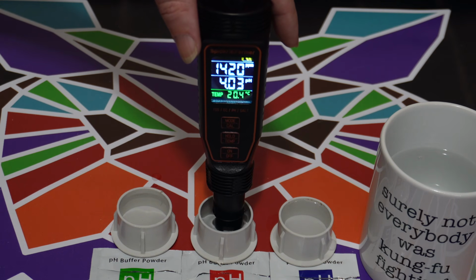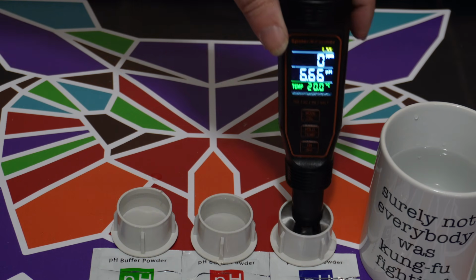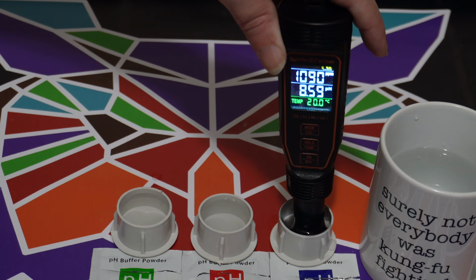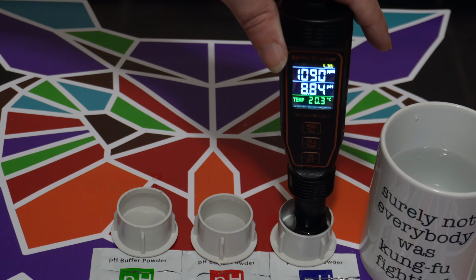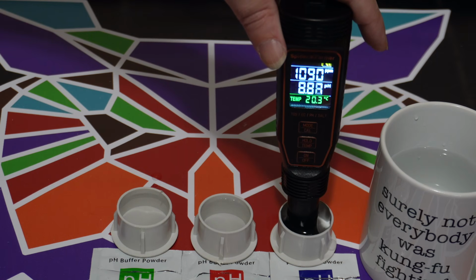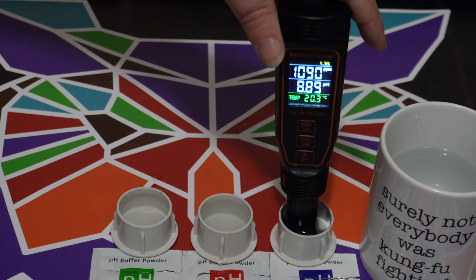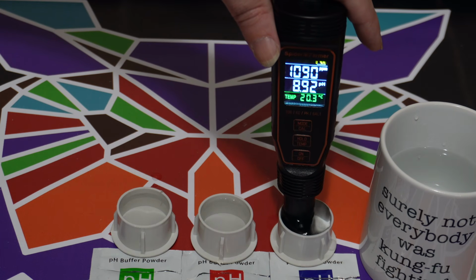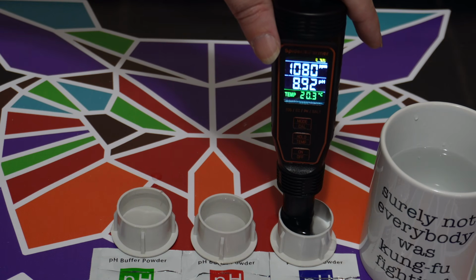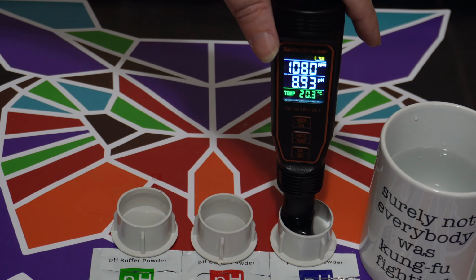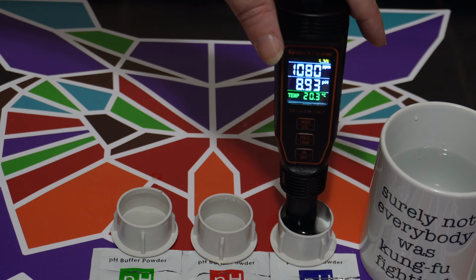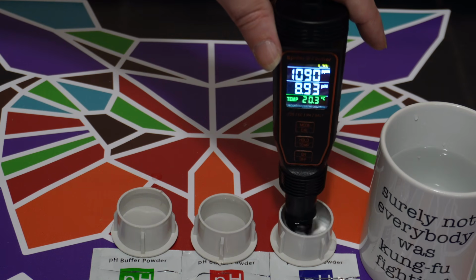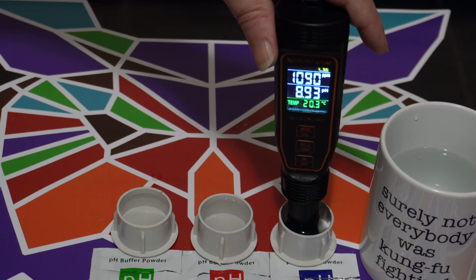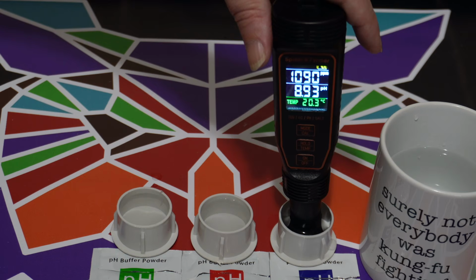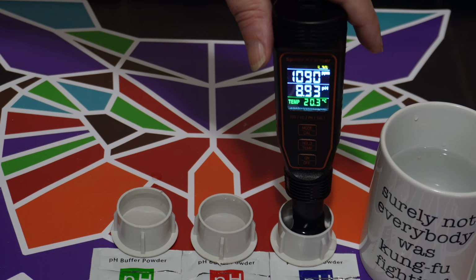So let me rinse this off and we'll just double check it with that 9.18. All right, and here's that final, just double checking it after we calibrated it, dipping them in all the solutions once again. And this should rise up from that 4.03 up to this 9.18. So we'll see if there's a little bit of variability at this end of the scale as well. Because again, that 6.86, which is the middle for living soil, shoot, that's great. That is your goal. But realistically, hydroponics, coco, that is in the upper fives, 5.7 to 5.9. Some even go to the 6.2. But this is now reading 8.93. Let's give it a second here, mix it around, see if it adjusts any closer to that 9.18. And it's looking like it's sticking at that 8.93.